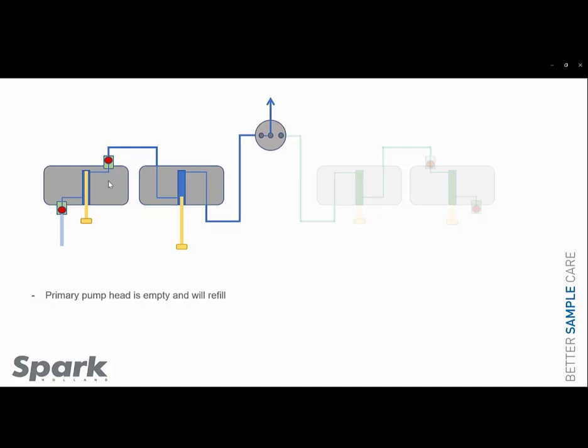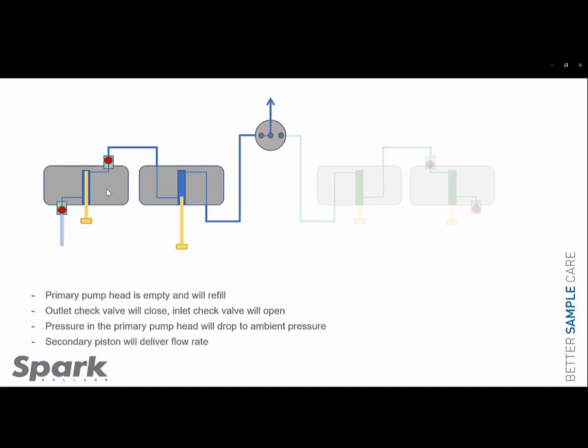The primary pump head is now empty, and it will refill. The secondary pump head is ready to deliver its system flow rate again. The outlet check valve will close, and the inlet check valve to aspirate the mobile phase will open. The pressure inside the primary pump head will drop into ambient pressure. The secondary pump head will deliver its flow rate.